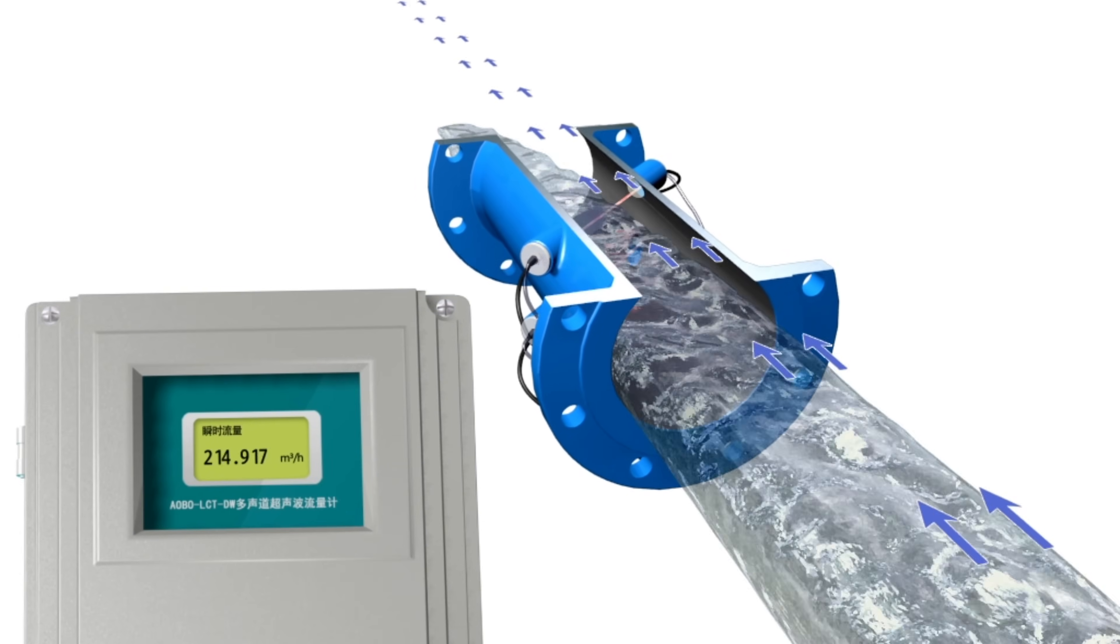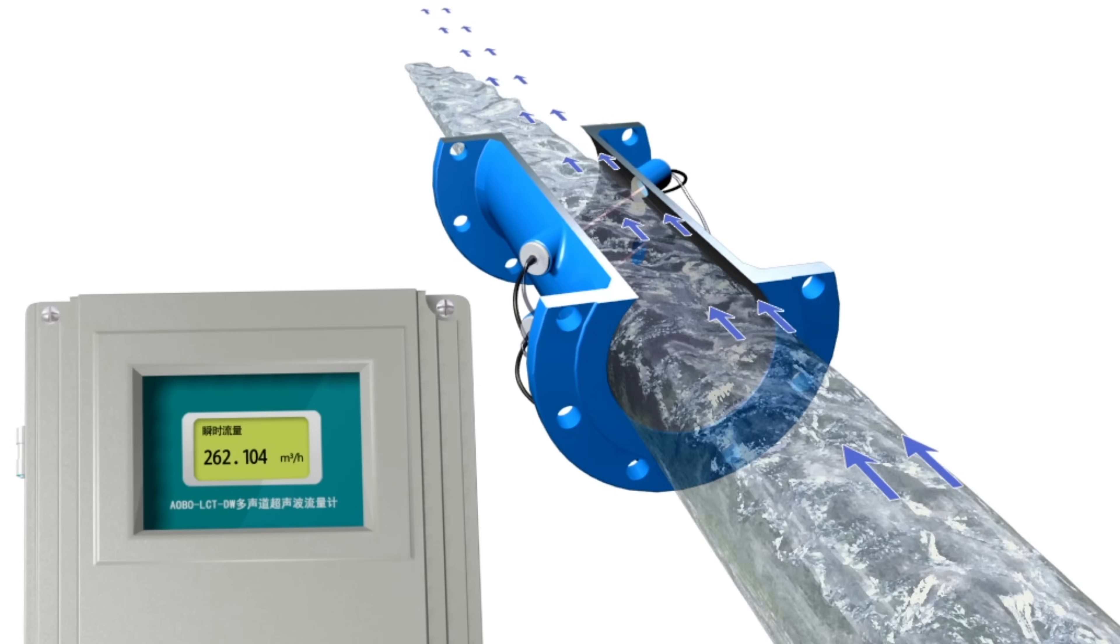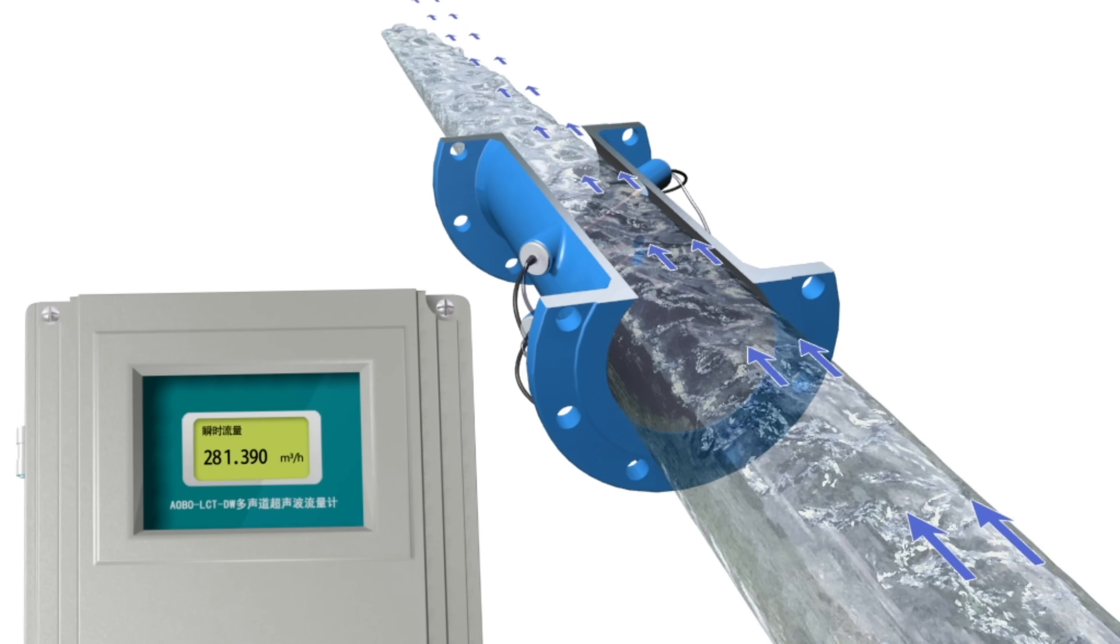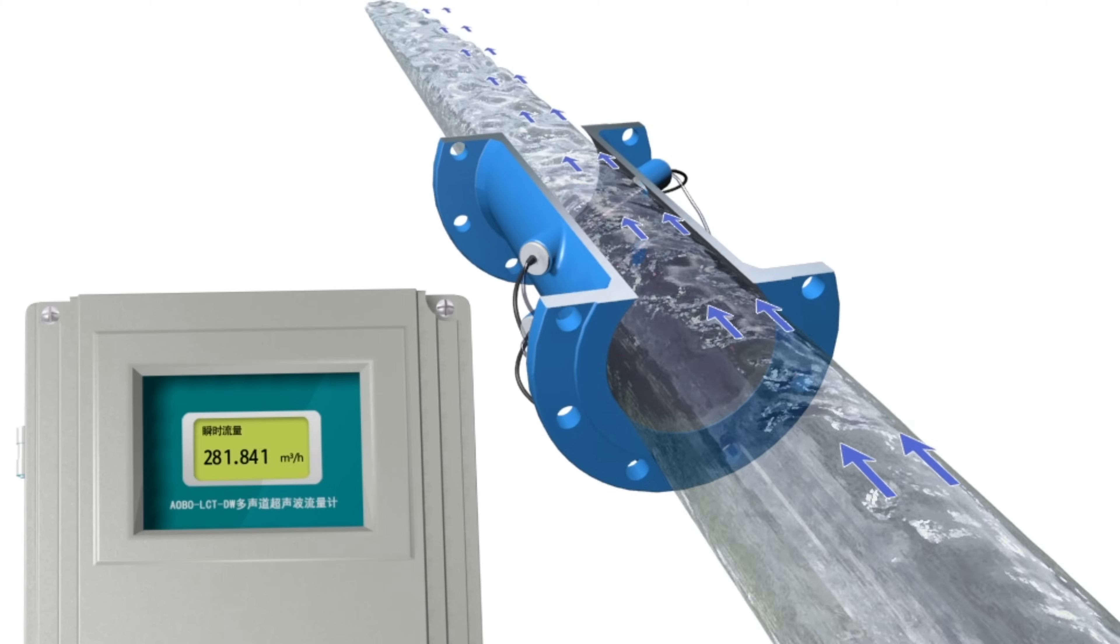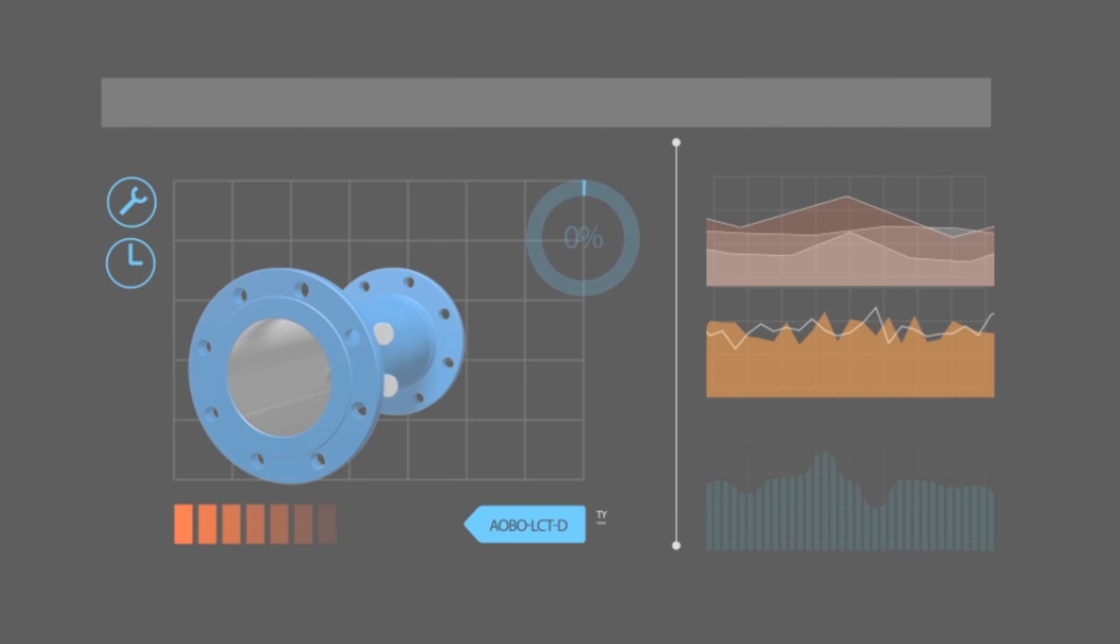Linearity is less than 0.5%, repeatability is less than 0.1% within the flow rate range of 0.015 to 5 meters per second.